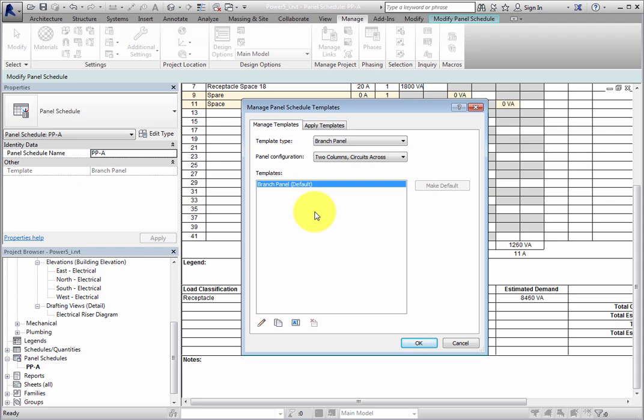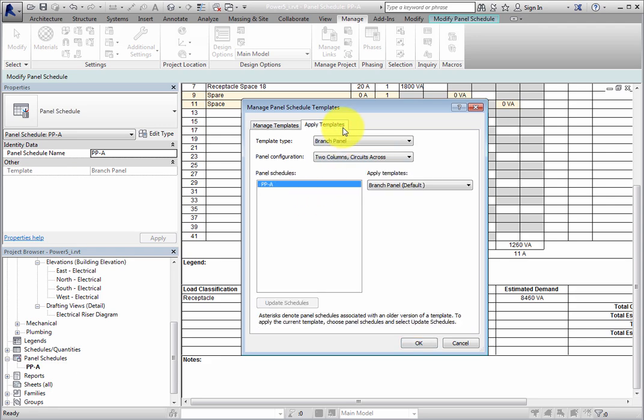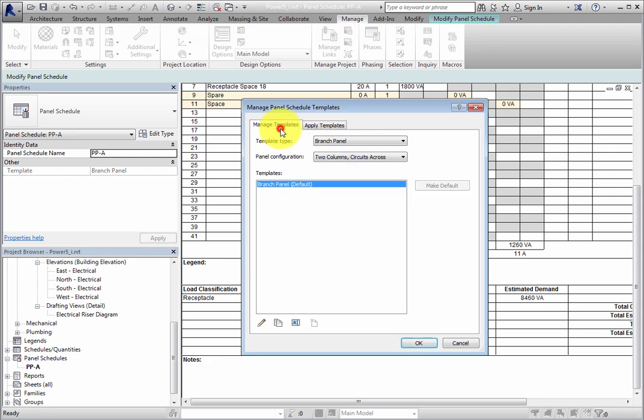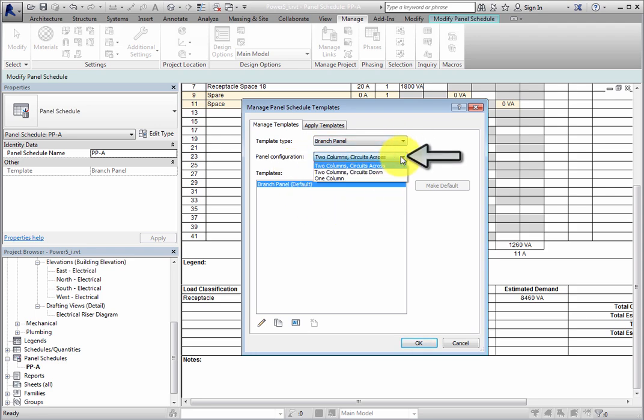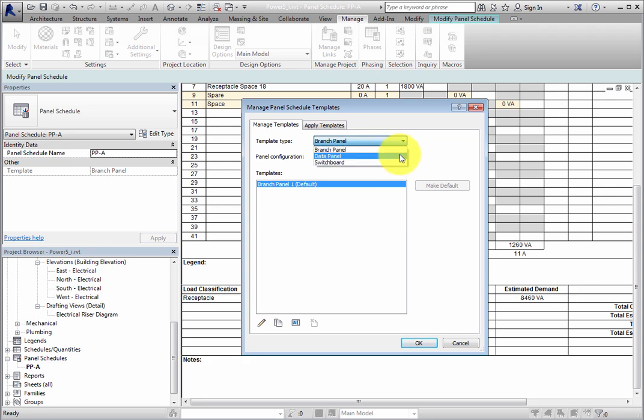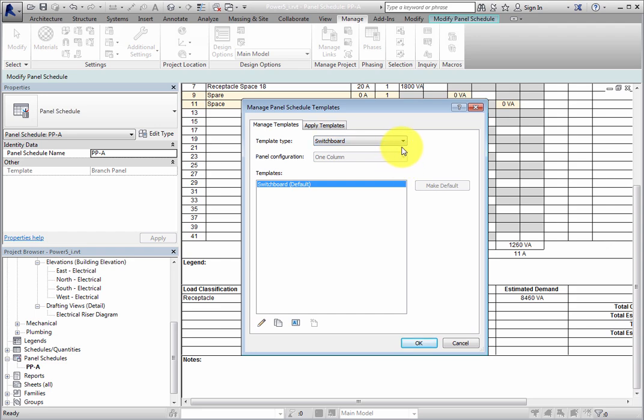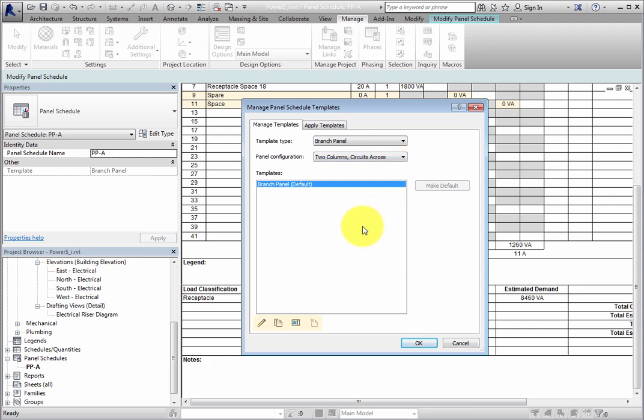There are two tabs here: Manage Templates and Apply Templates. On the Manage Templates tab, you can select a template type and panel configuration to see the templates of that type and configuration. The panel configuration is only available for the branch panel type. You cannot select a configuration for a data panel or switchboard. With the type selected, the templates appear in the Templates list. You can use the buttons at the bottom to edit, duplicate, rename, or delete the template. However, you cannot delete the default template. If you had more than one template, you could select which template is the default.